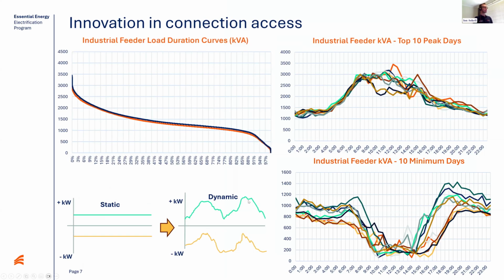So talking to an example of the dynamic connection arrangement that the Future Networks team is currently working on - this figure presents a load duration curve for an example industrial facility on our network, an industrial feeder. A load duration curve, as I mentioned before, is basically if you look at 365 days in the year and sort that demand from largest to smallest, it helps us assess the utilization of that asset. This is a total feeder, and as we can see, for the majority of the year the network is sitting below that peak demand.